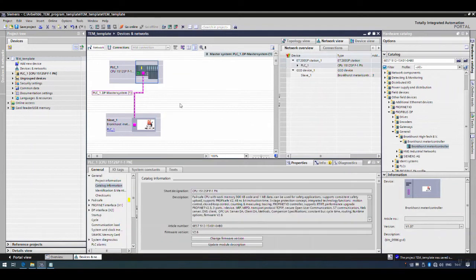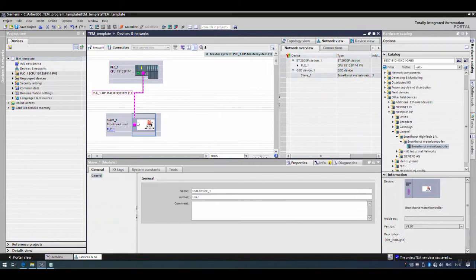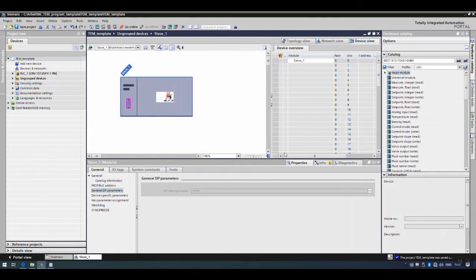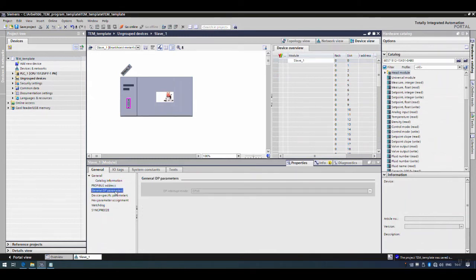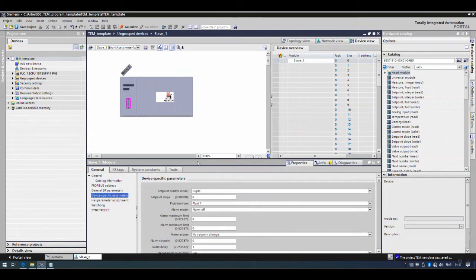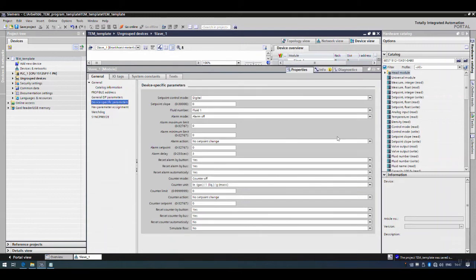Going to properties, the PROFIBUS address is shown — for this example I will set the address to 4. Under general DP parameters there are different types of PROFIBUS; here we are using DPV0. Device-specific parameters are very important — please review the key parameters that are commonly set for this MFC to work, highlighted in yellow in the manual.